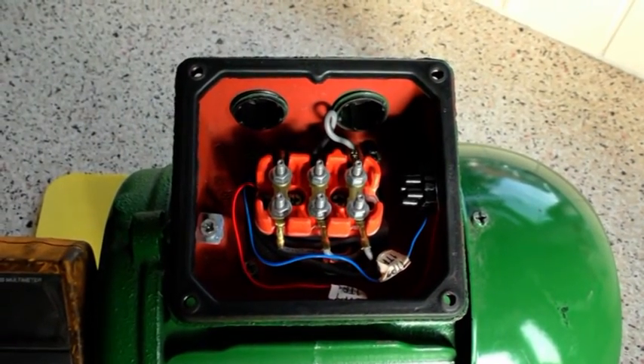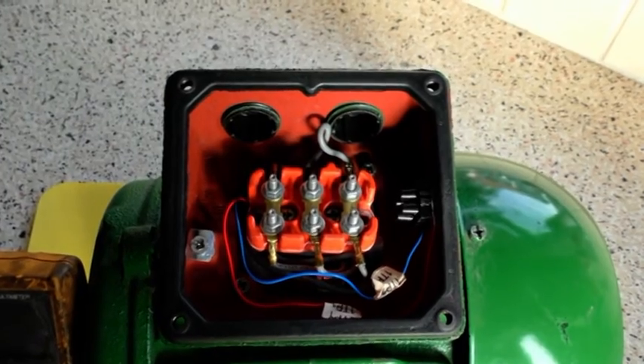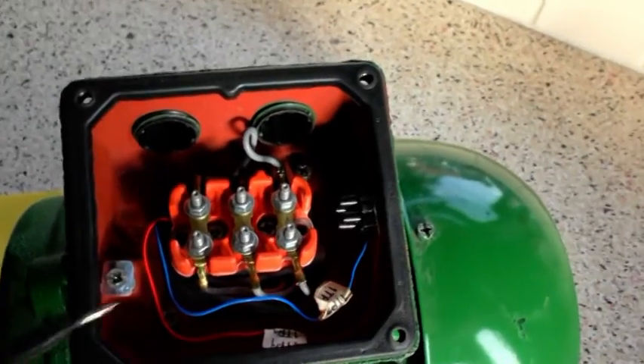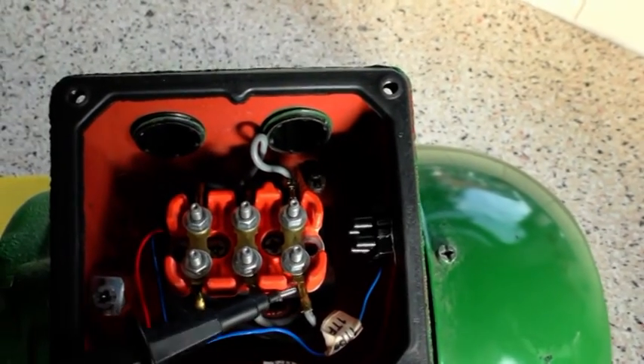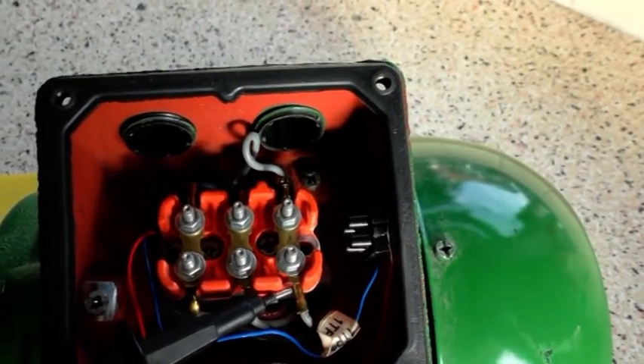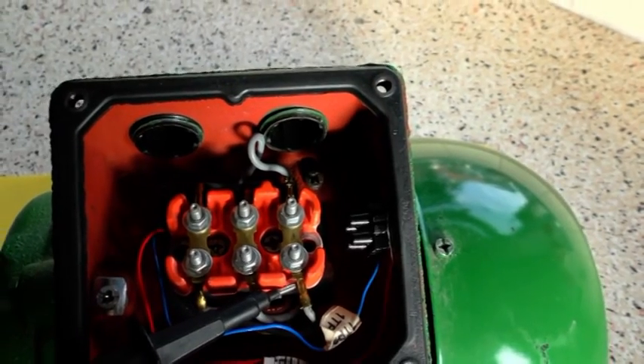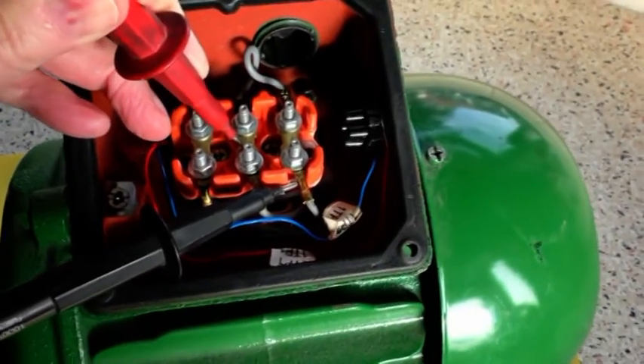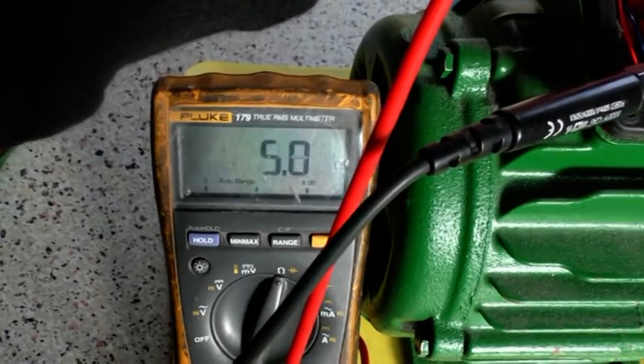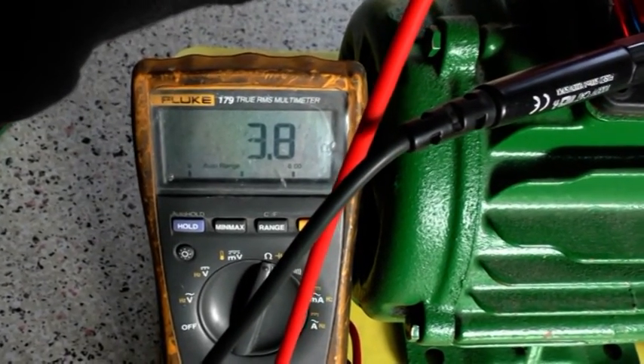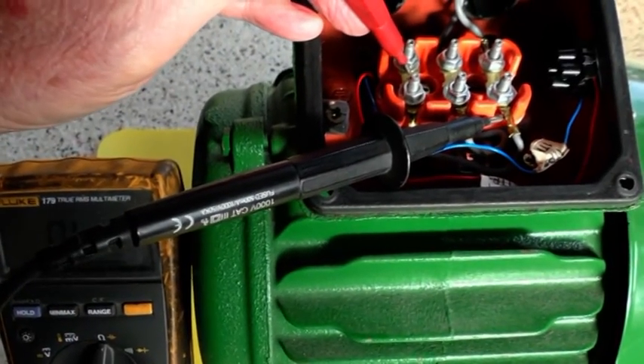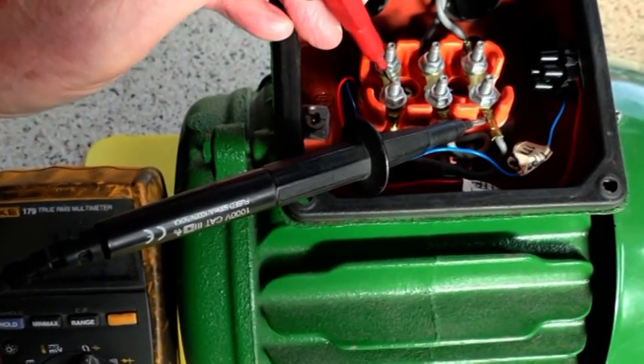Okay so I've tested these windings. These windings are approximately 6 ohms as we used in our calculations. So I'm going to put one lead here under the W and then if I touch the other probe here we should get a value around about 4 ohms and if we look at the meter we're getting about 4 ohms plus or minus the 10% or give it a little bit for the resistance of the terminations.